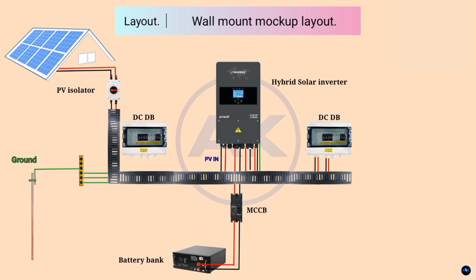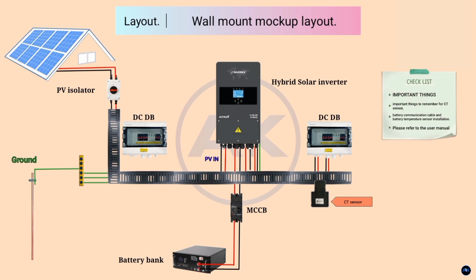And of course the CT sensor, with the arrow pointing to the hybrid inverter. That's the CT sensor. Important things to remember for the CT sensor, battery communication cable and battery temperature sensor installation: please refer to the user manual. If you don't have net metering provided by your power company, make sure the arrow is pointing towards the inverter. Otherwise, for all the energy that you export back to the grid, you will have to pay for it as consumption.